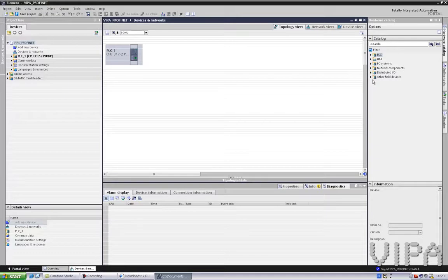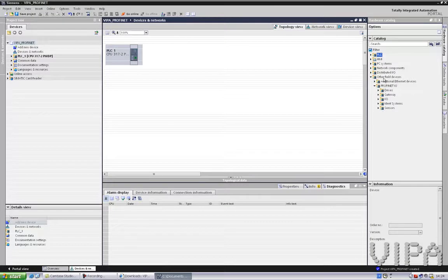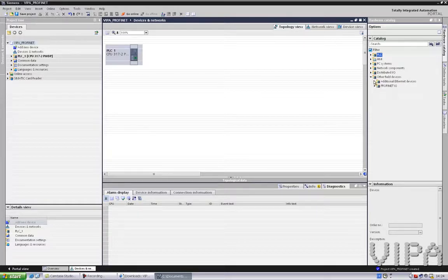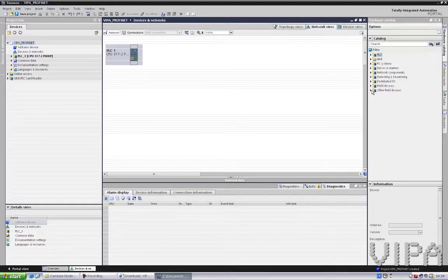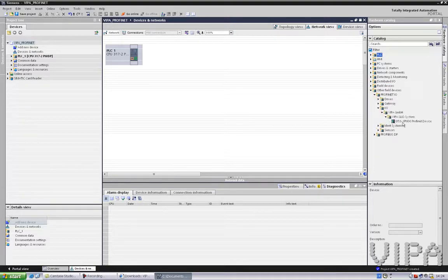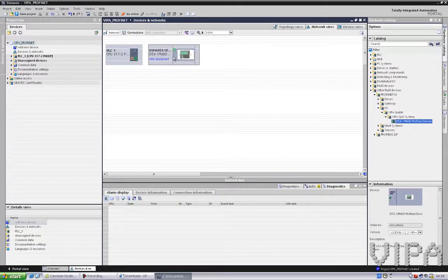Once the GSD file is installed, you can find our SLIO coupler within Additional Field Devices, Profinet I/O. There we go — I should be able to see it over here. Network view, field devices, Profinet I/O. There we go. I can double-click this one and then make a connection, like this.